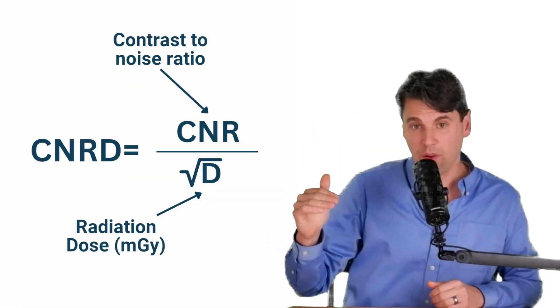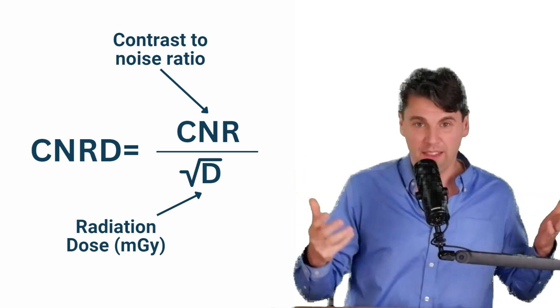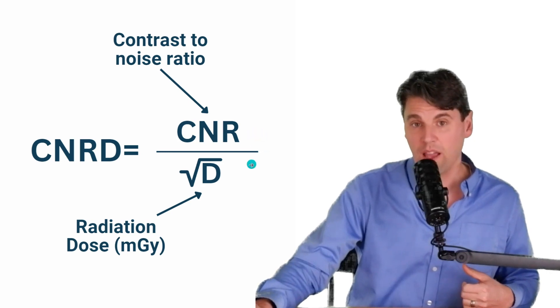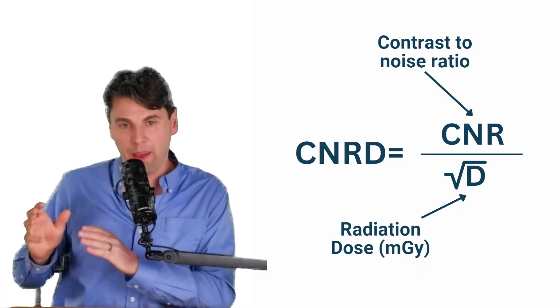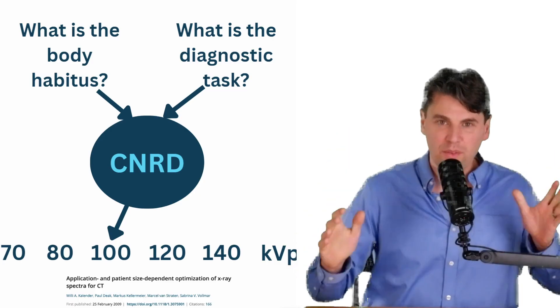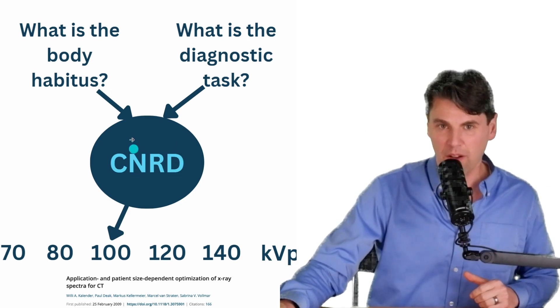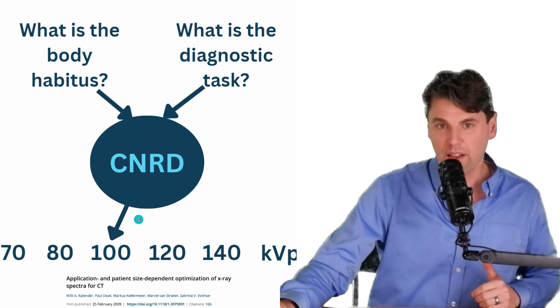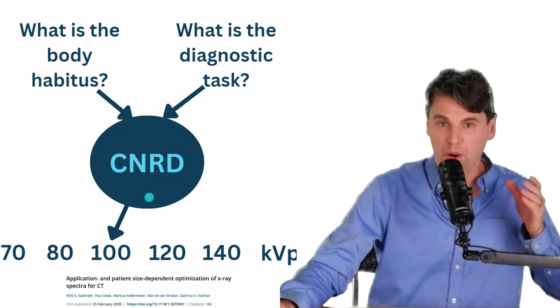That contrast divided by the noise, we can also just call that the contrast to noise ratio. We've had videos on the channel before about what contrast noise ratio is. If we have the contrast noise ratio, then we divide that by the square root of the dose. It's basically saying, under what conditions are we going to get the best image quality for a given dose level. So now we don't have to have Willie sitting here answering the question, we can actually just use our model that says given a body habitus and given a diagnostic task, what's going to be the best KVP based on the contrast to noise ratio per given dose.